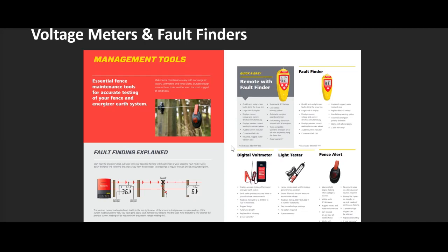Again, hold it on the fence. If there is any faults, it displays it with an amperage, and then you sort of walk along the fault or walk along the fence. Every time you come to a connection, hold the device on both sides of the connection, and you follow the highest amperage to find where the fault is. And they do work really well.